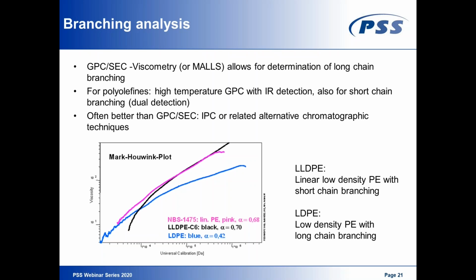What I cannot measure with GPC SEC viscometry is short chain branching. Here you see also overlaid linear low density polyethylene, which exhibits short chain branching, and you will see that our viscosity detector is blind for the branching here. Short chain branching is not affecting the viscosity so much that we can measure it using the GPC SEC viscosity detector.